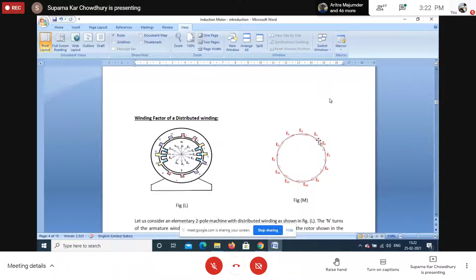So when we are making the winding, say we are making the coil with conductors 1 and 7, 1 and 2 and 7 and 8. For conductors 1 and 7, the EMFs are 180 degrees opposing. But if we trace this coil, then they are basically added up, so the summation will be E1 plus E7. For E2 and E8, the summation will be E2 plus E8. But these E1 plus E7 and E2 plus E8 are gamma degrees apart.